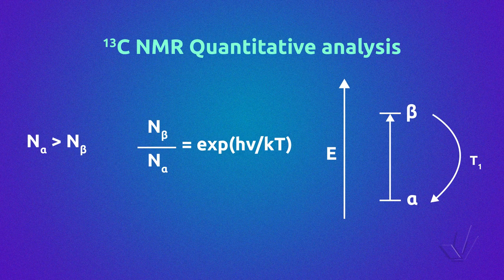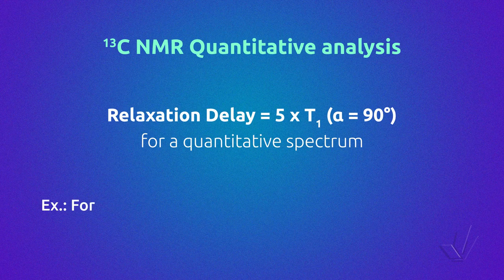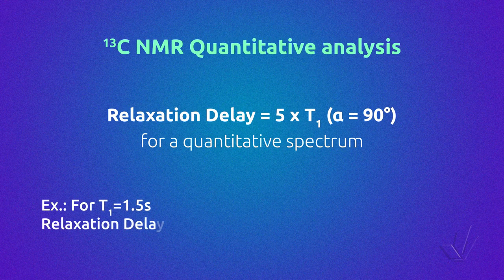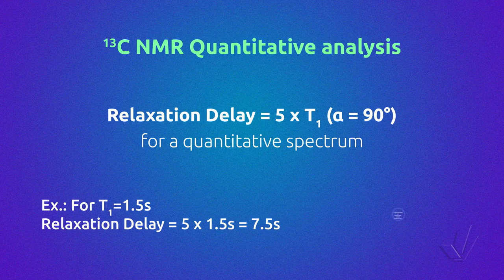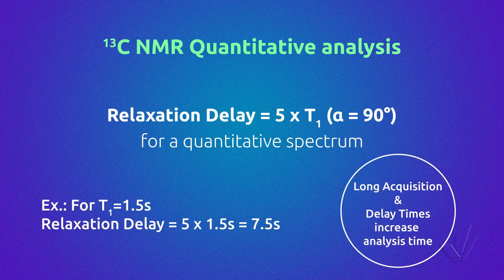It has been established that for a quantitative carbon spectrum, a relaxation delay of five times the relaxation time of the carbon atoms must be applied, for a pulse angle of 90 degrees. So if a carbon atom has a relaxation time of 1.5 seconds, the relaxation delay should be 7.5 seconds. The problem is that long acquisition times and relaxation delays enormously increase the time of an NMR analysis.